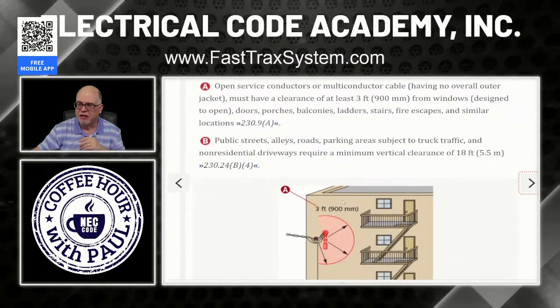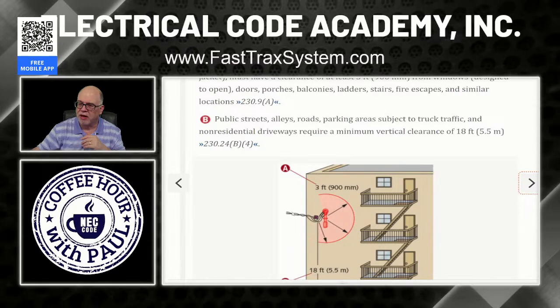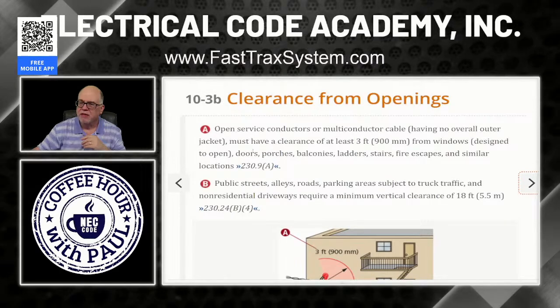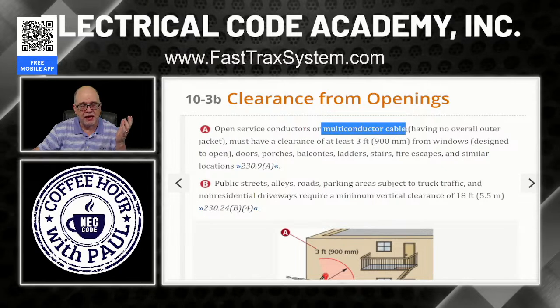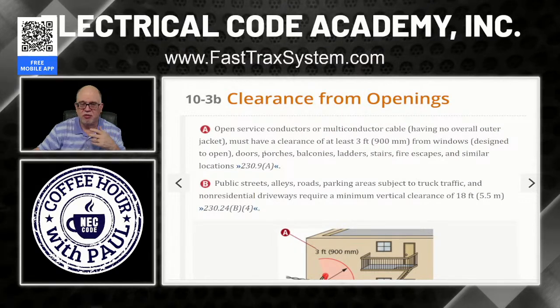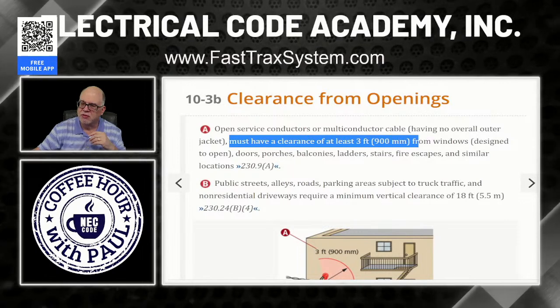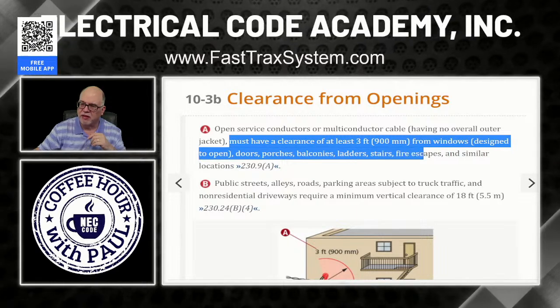Again, great illustrations. So let's look at A. A is pointing right here to the 3 feet. So here's our service drop right here. And we see it's connected to the side of the building. It says open service conductors or multi-conductor cables. This could be a service drop cable. Okay. It has no outer covering. They're just exposed conductors. It says must have a clearance of at least 3 feet from windows designed to open. That's important. Doors, porches, balconies, ladders, stairs, fire escapes, and similar locations. Where is that covered? 230.9(A), that's a chevron.